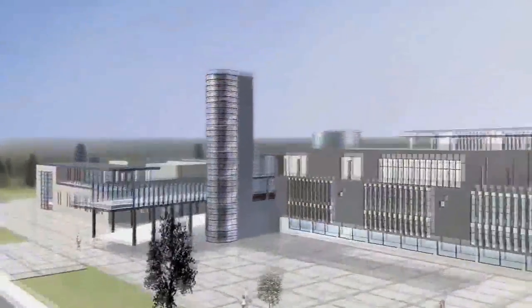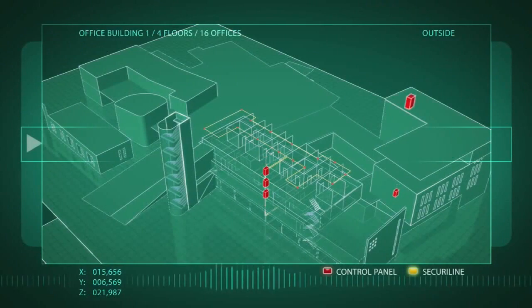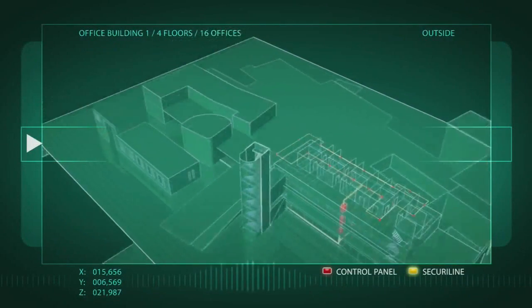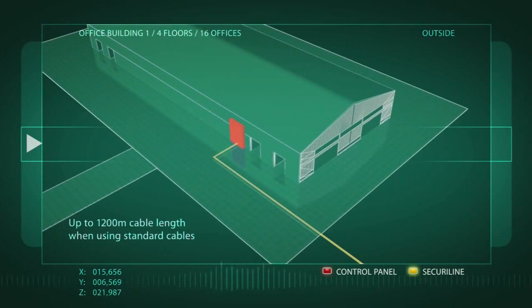For each area of your building, a separate control panel is deployed for each floor or section. From this unit, up to 16 detector loops lead through the individual rooms, which are equipped with the appropriate number of fire detectors and other addressable units.